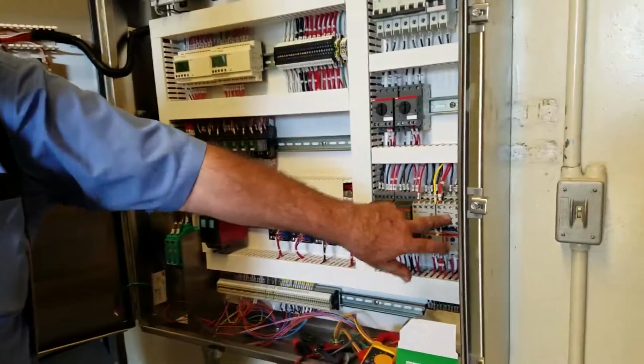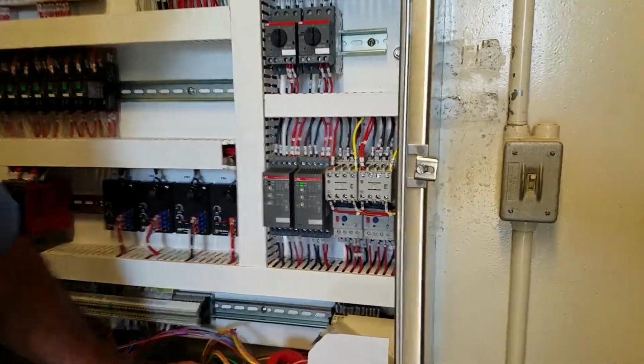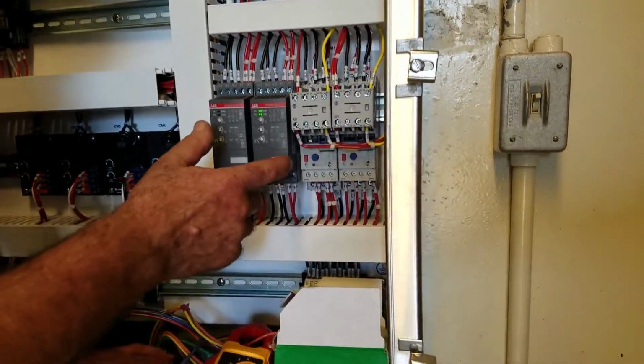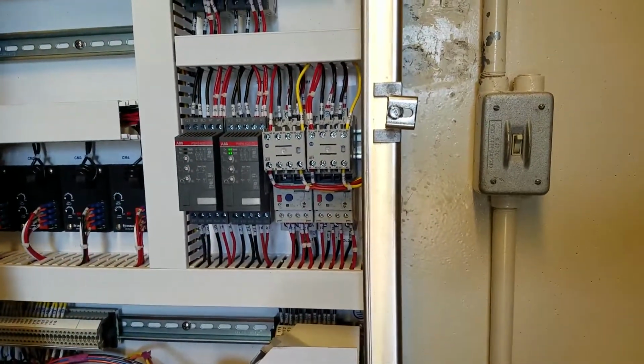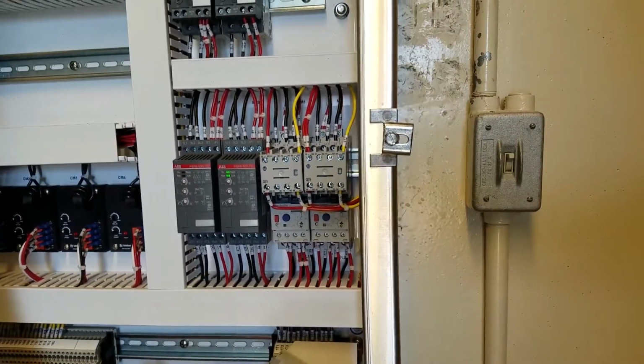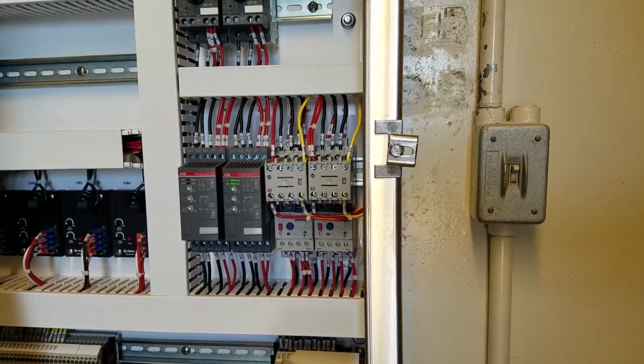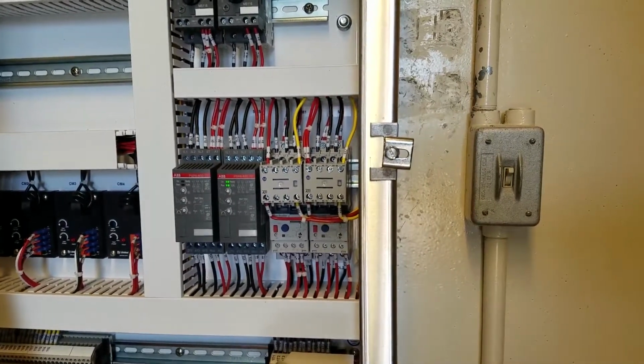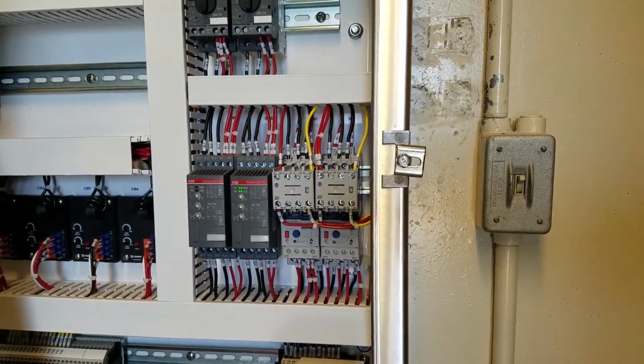These are your motor starters. These are your overload relays. If you have to come in here and push the reset button on one of those, you better have somebody with electrical expertise go in and check for loose connections and things like that. Make sure you got a problem.